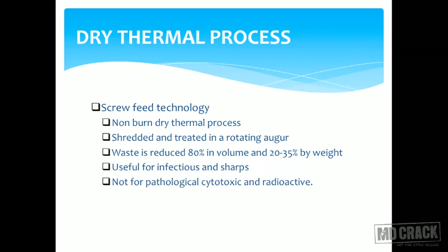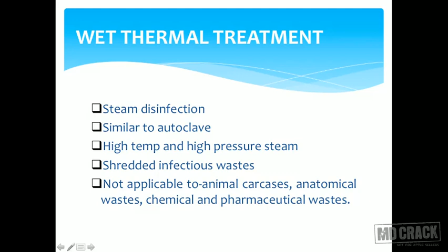Wet thermal treatment is basically steam disinfection, similar to autoclaving as studied in microbiology. High temperature and high pressure steam is used, and it can be applied to shredded infectious waste. It is not applicable to animal carcasses, anatomical waste, or chemical and pharmaceutical waste, following the same logic that these won't respond well to wet thermal treatment.